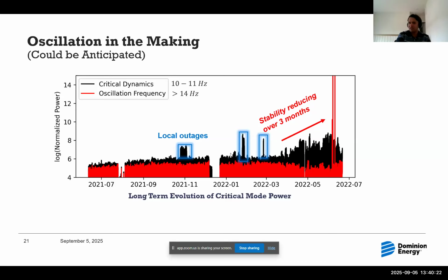But what is interesting, what we could not explain, was that in the 3 months leading to the oscillation week, you can see a gradual increase, or gradual deterioration in stability, of the 10 to 11 hertz dynamics. We have a 10 to 11 hertz mode, but it gradually becomes worse, and towards the end is where you start seeing oscillations, given by these vertical peaks in the red plot - the power in the signal in the 14 to 15 hertz range.